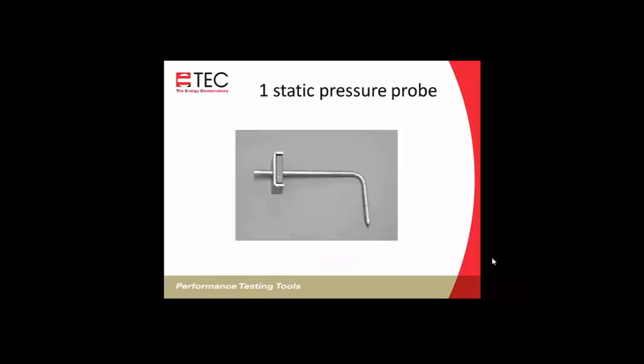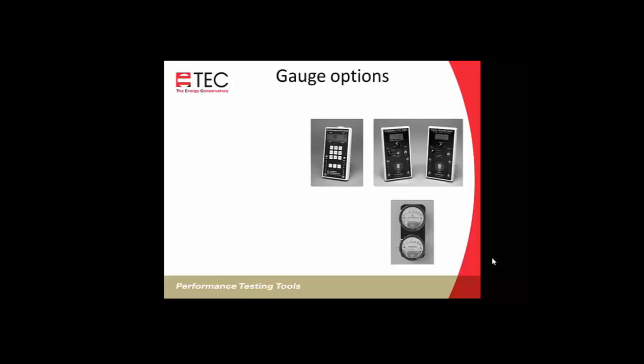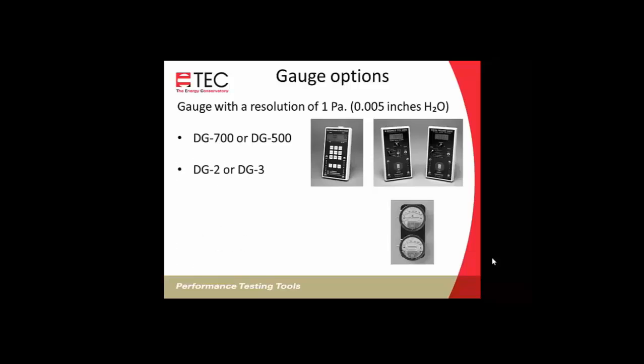Also includes a static pressure probe that's got a magnetic connection to attach to the side of a plenum. And gauge options, again, gauge resolution of 1 Pascal or 0.005 inches of water, which would be a DG700, DG500, DG3, or DG2. Other digital manometers, there's a lot of other manometers out there that would meet this resolution of 1 Pascal requirement, or a magnehelic gauge.